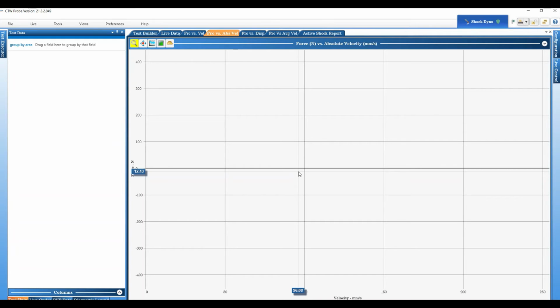Basically, this sets the stroke, because everything in the dyno, the software, when you tell it a speed, it's all based on the stroke. Now, you should be able to look at the actuator going up and down. You should be able to tell what stroke it's on. You can always use a ruler, measuring stick, anything to tell how far it's actually moving, kind of a second verification. But when it's done, it's going to stop, and it's going to tell you what it thinks the stroke is. It thinks the stroke is 26 millimeters, which is correct.